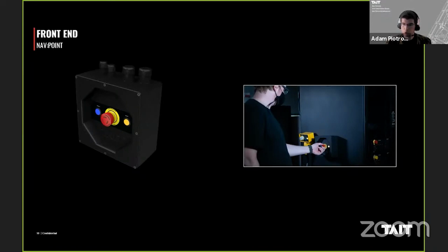Certainly you want them at your operator position, but maybe you have a machine room with all your winches in it, so you need a way to stop them during maintenance, or maybe plug in your maintenance pendant. Putting these in strategic locations is part of the control system design, to ensure good control of the system and good points for spotters or anyone who can see an issue, like someone not being where they're supposed to be, so they can hit that e-stop button or anything else like that.